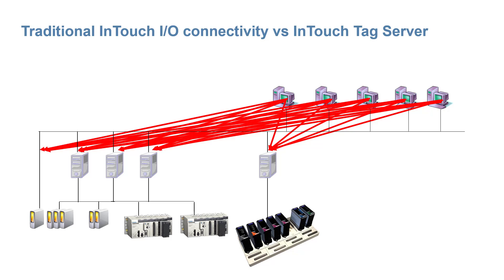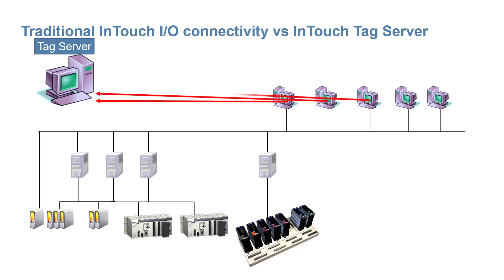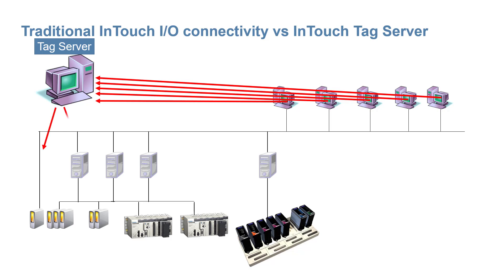The solution is the tag server. A tag server centralizes the point-to-point IO communications. This means that each visualization node need only make a single connection to the tag server. The tag server then makes a connection to each data source.